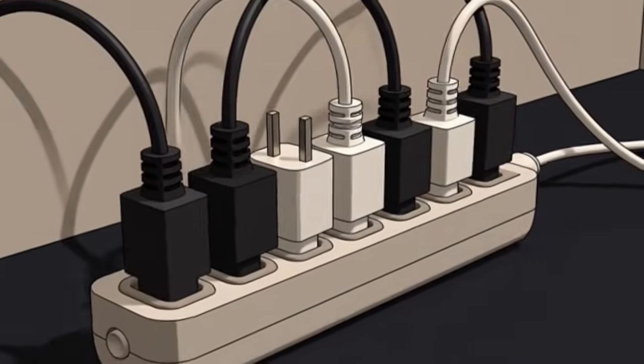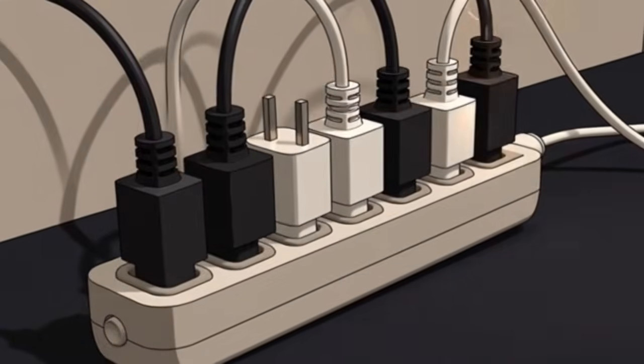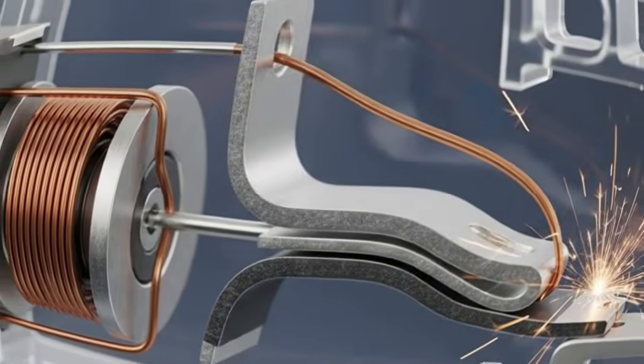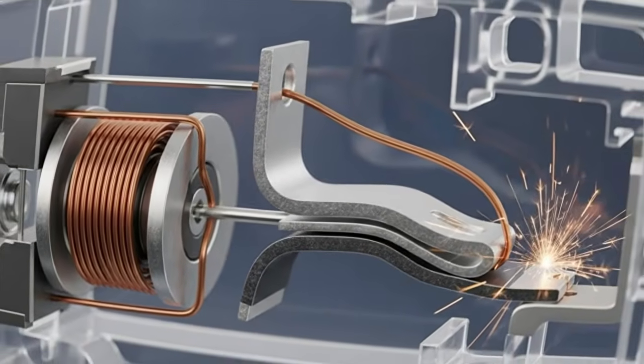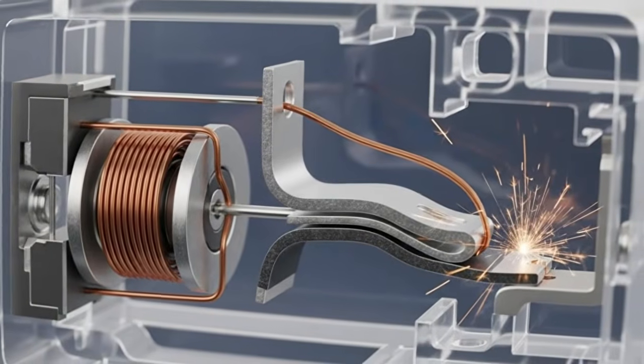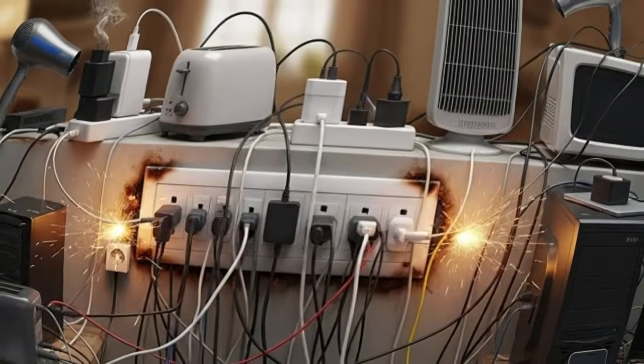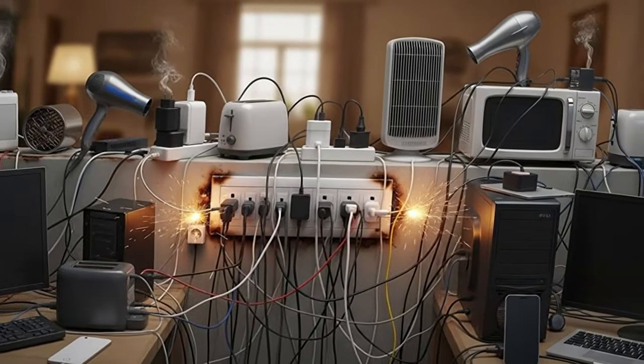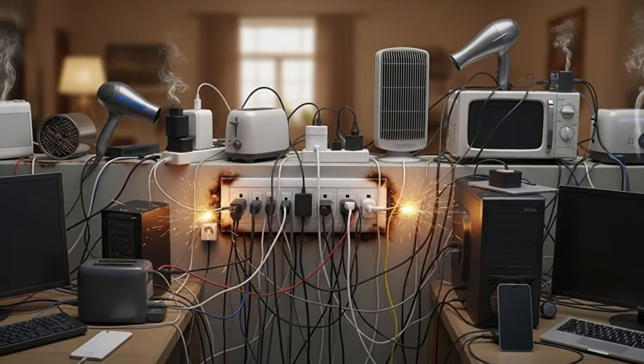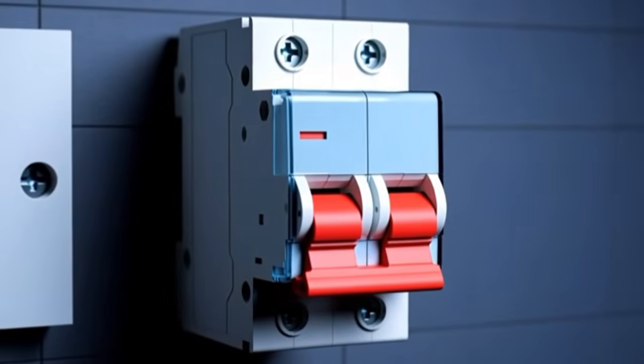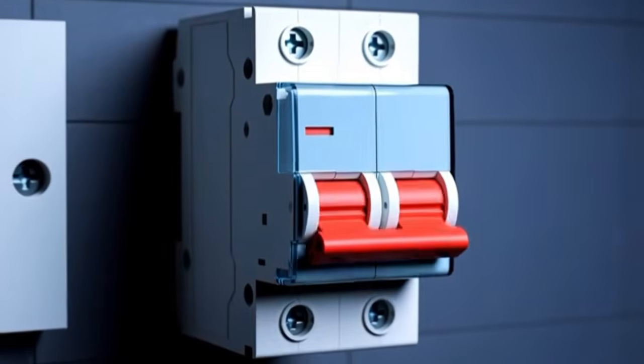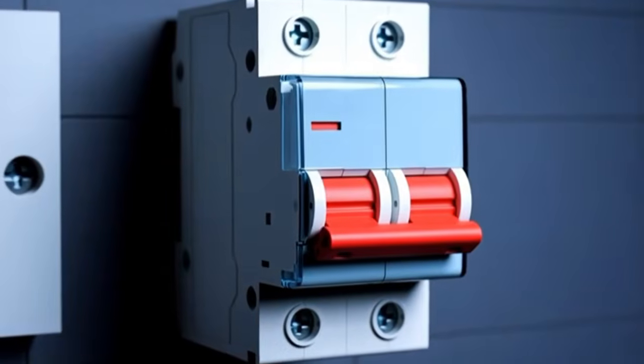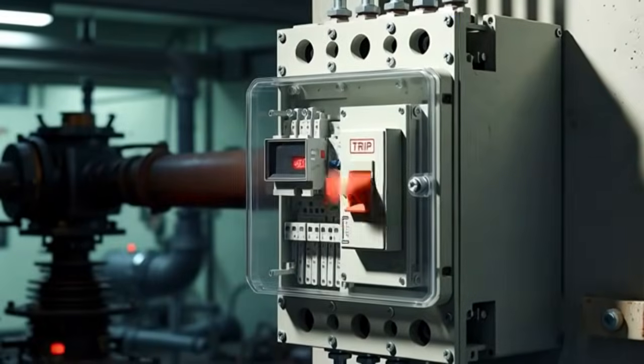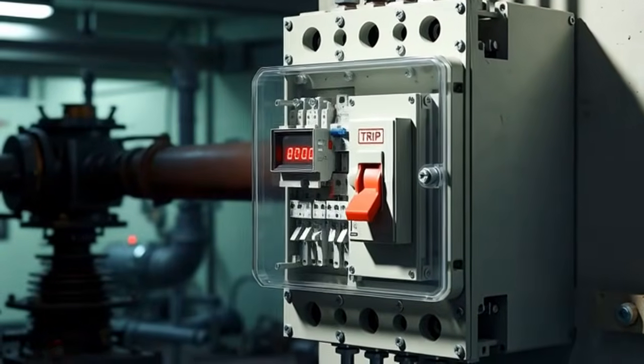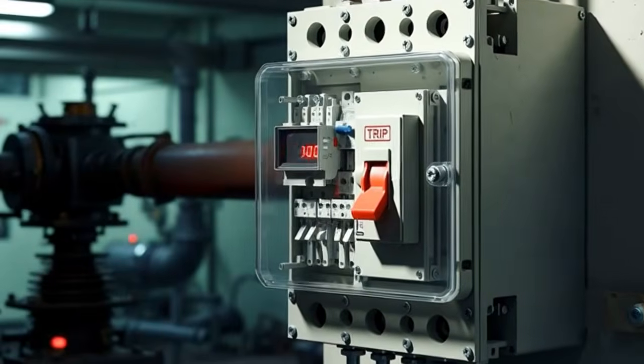With a pure overload, the breaker usually trips after running for a while, not instantly. The bimetallic strip inside the breaker heats up gradually and eventually bends enough to trip the mechanism. But here's where overloads can prevent a breaker from resetting. If the overload condition still exists, if all those devices are still plugged in and ready to draw power, the breaker may trip again almost immediately when you reset it. The wires are still hot from the previous overload. The breaker's bimetallic strip is already warm. Current surges in and the breaker trips before you can even take your hand off the panel.